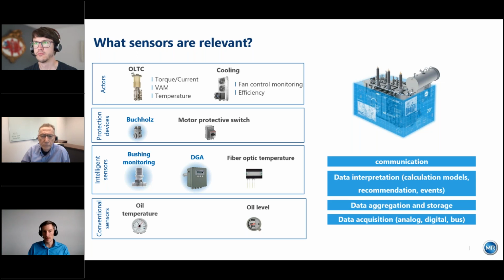If you only had 3 sensors or 3 data generators on transformers, what would they be? We would recommend to always have DGA, bushing monitoring, and a Buchholz relay, ideally one with a warning level. Those 3 can really provide very accurate diagnostics within the Bayesian network. Of course, everything will be connected and other systems will also help make diagnostics more reliable, but if you only had 3, those were the 3 with the biggest impact.